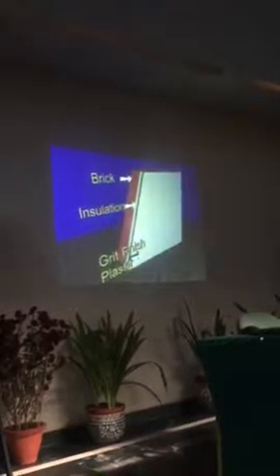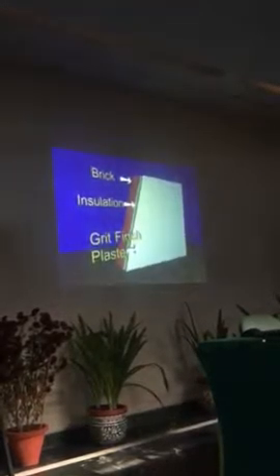Use of insulation on vertical walls and roof, finished with China mosaic flooring on the roof, has drastically reduced the building heating and cooling loads. Through the provision of daylight-friendly design features, the need for artificial lighting in any of the rooms has been virtually eliminated. Appropriate passive solar design concepts were combined with efficient space conditioning and lighting design to bring down the connected load from 280 kilowatts to 96 kilowatts.